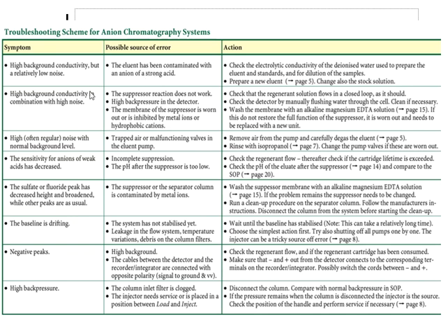High background conductivity in combination with high noise. This is a sign that your suppressor is not working. It's also a sign of back pressure in the detector. And it's also a sign that the membrane of the suppressor is worn out or is inhibited by metal ions or hydrophobic cations. A lot of times what you're seeing here is suppressor related.